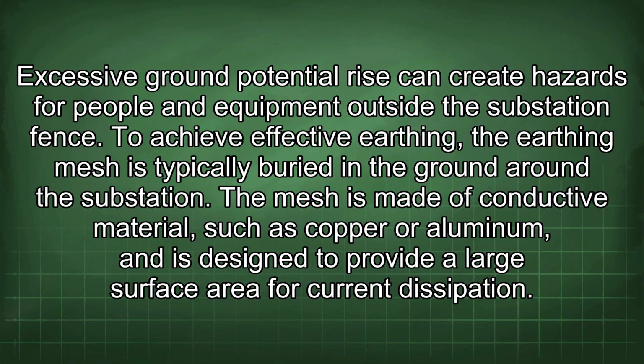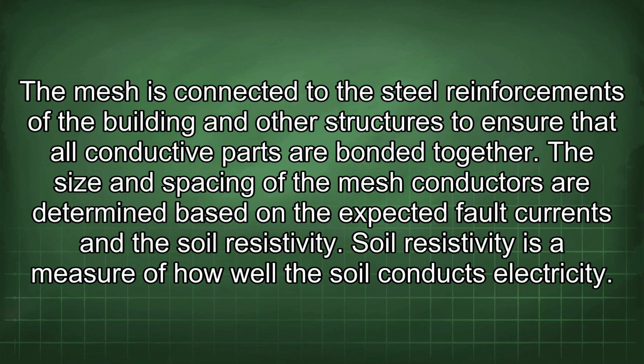To achieve effective earthing, the earthing mesh is typically buried in the ground around the substation. The mesh is made of conductive material such as copper or aluminum and is designed to provide a large surface area for current dissipation. The mesh is connected to the steel reinforcements of the building and other structures to ensure that all conductive parts are bonded together.